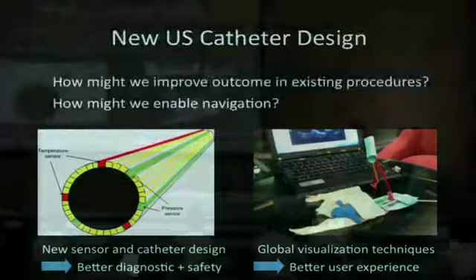So we basically took the existing CMUT design that was previously used, and made simple modifications to incorporate the thermal sensors and also the piezoelectric pressure transducers. And as was mentioned earlier, the reason for these is that it's great to have an image as we're going down the vessel, but there's so much more information you can gain. For example, if you encounter a bend and you're putting a lot of force into the push, you could, depending on the force, damage the vessel wall. So it was important to gain as much information as possible so that the operator of the device can have the feedback and be aware of what is going on.